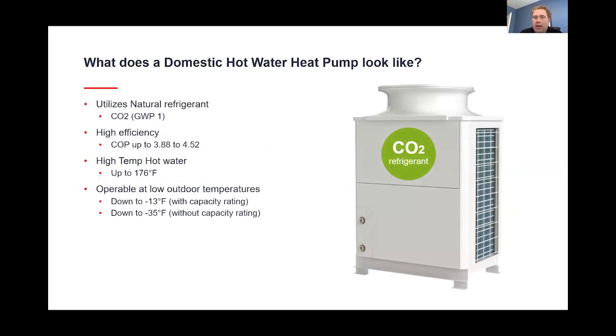So now we're going to jump into the actual domestic hot water product. And what does a domestic hot water heat pump look like? So it can produce 176 degree water all the way down to negative 35 because of the CO2 refrigerant. It's going to have COPs from 3.88 to 4.52, utilizes the natural refrigerant of CO2, and they can operate down to negative 35. And depending on the manufacturer, some will operate down to negative 4 and require backup electric heat for colder climates.